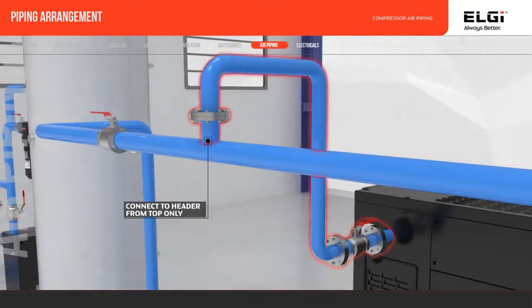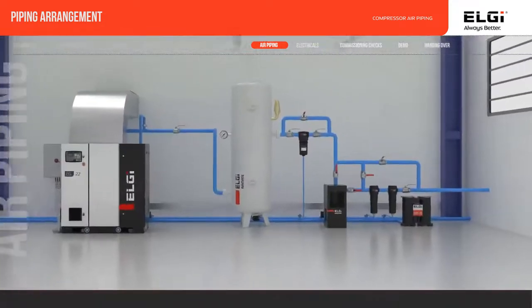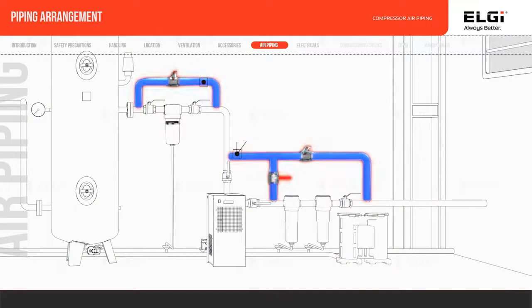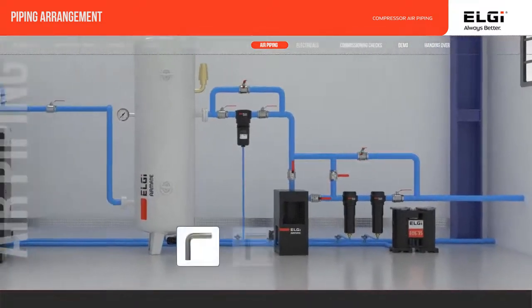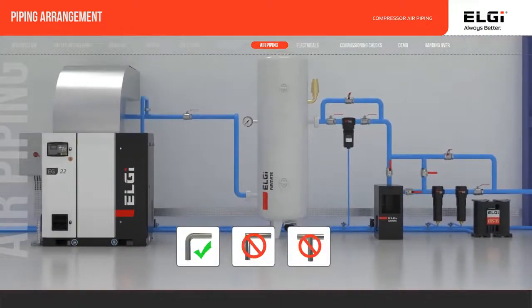Compressor air outlet should be connected on top of the common or main header pipe to avoid condensed water entry when the compressor is idle. Provide the bypass piping arrangement for dryer and downstream filters in case of isolation or emergency. Try to use long bends and reduce the number of bends in the pipeline as much as possible to avoid pressure drop.